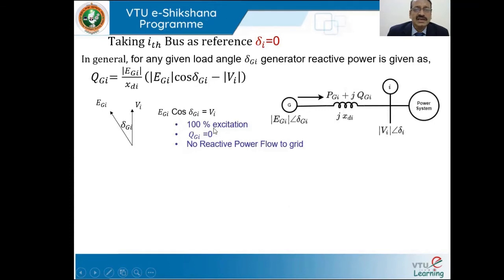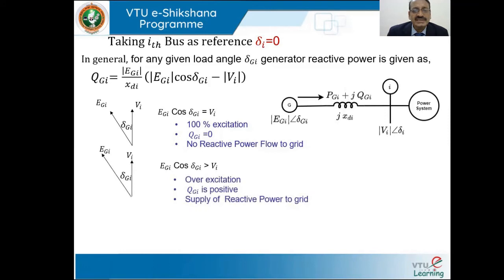When EGi × cos(delta_Gi) equals Vi, this condition is called 100% excitation, where QGi equals zero and no reactive power flows to the grid — this corresponds to unity power factor operation by the generator. When we overexcite the generator, EGi magnitude is greater than Vi, so EGi × cos(delta_Gi) is greater than Vi. This is overexcitation, and QGi becomes positive, meaning the generator is supplying reactive power to the grid.